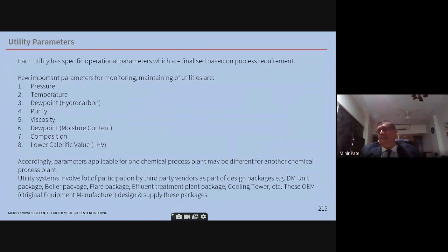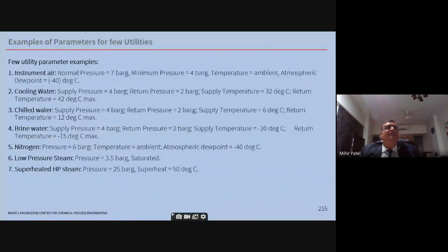Utility parameters. Each utility has certain parameters which have to go with the basis of design. So what are these parameters? Here you can see pressure, temperature, dew point, purity, viscosity. These are things you need to specify so that you can design the system accordingly, and the vendor can give the packages accordingly. In the next slide, you see examples. Instrument air: normal pressure, minimum pressure 4 bar, temperature, atmospheric dew point. Cooling water: what are the parameters? These are all parameters for the different utilities you encounter in the package.